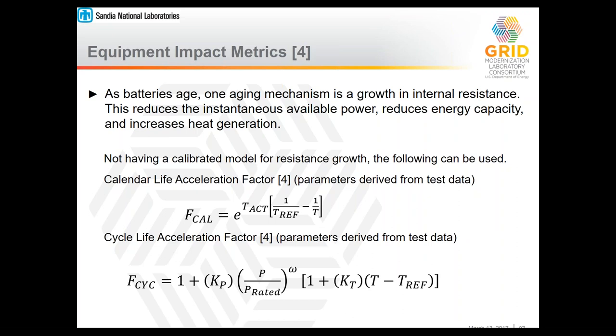Once you've done that, now I'll get into the equipment impact metrics. For all of these devices, whether it's a battery, an HVAC system, or potentially, as Savita mentioned, it's possible there are some age acceleration factors that these advanced functions have on inverters, that using them in a different way perhaps could accelerate how quickly they are degrading. And as batteries age, one of the aging mechanisms is a growth in internal impedance or resistance. This is the batteries becoming more electrically resistive over time, and that eats up a little bit of power, and that generates a little bit more heat. And so it's one of the ways that batteries degrade over time.